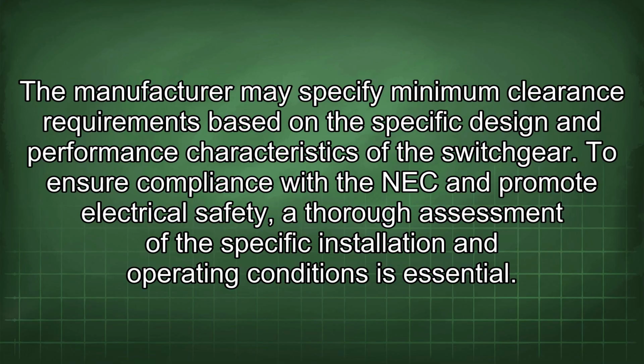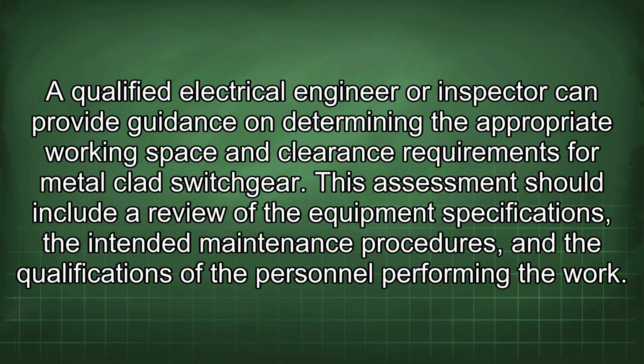To ensure compliance with the NEC and promote electrical safety, a thorough assessment of the specific installation and operating conditions is essential. A qualified electrical engineer or inspector can provide guidance on determining the appropriate working space and clearance requirements for metal-clad switchgear. This assessment should include a review of the equipment specifications, the intended maintenance procedures, and the qualifications of the personnel performing the work.